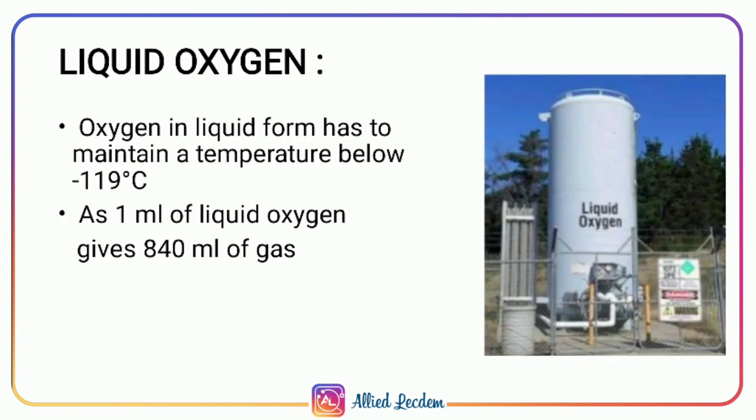Oxygen can also be stored in liquid form in large quantities in the manifold. The manifold is the area at the hospital from where gases at appropriate pressure are supplied continuously to all patient areas. The temperature is maintained below minus 119 degrees centigrade. More oxygen is obtained from liquid oxygen than from gaseous oxygen — 1 ml of liquid oxygen gives 840 ml of gas.